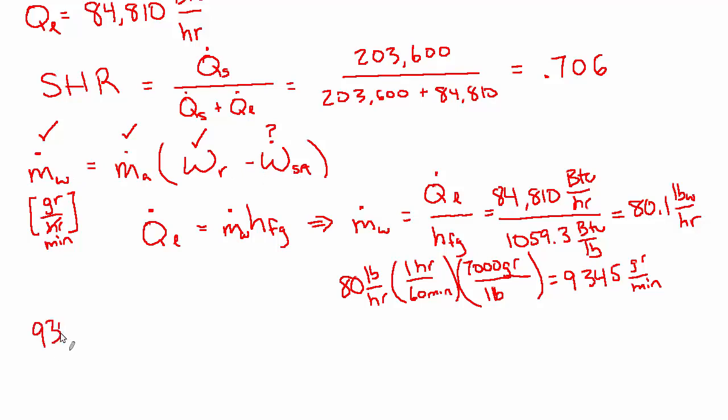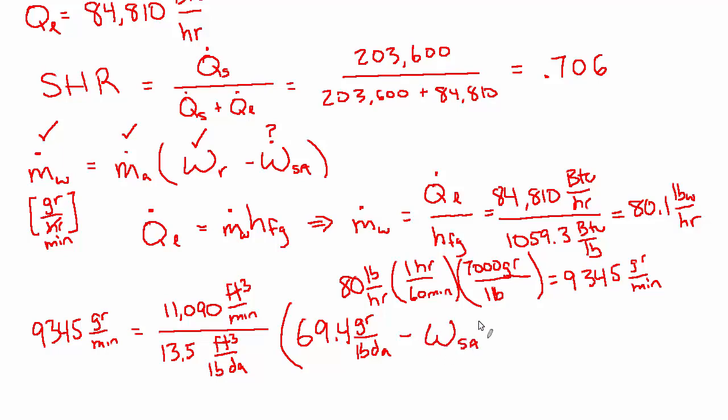Let's substitute into this equation. So 9,345 grains per minute equals the mass flow rate of air, which is 11,090 cubic feet per minute. I'll write it this way since we want to see the units cancel. And now we want to change that into pounds of dry air per minute, so we'll divide by the specific volume. And I'm just using this as a typical value—13.5 cubic feet per pound of dry air. I didn't even bother to look at the psych chart, it's just kind of a typical number, but you could probably be more precise here by looking up the exact room conditions. And then we're going to multiply that by the difference in the humidity ratios. The humidity ratio that is associated with a room that's 77 degrees dry bulb and 50% humidity from the psych chart is 69.4 grains per pound of dry air, minus the humidity ratio of the air being supplied, which we don't know. That's what we want to know.